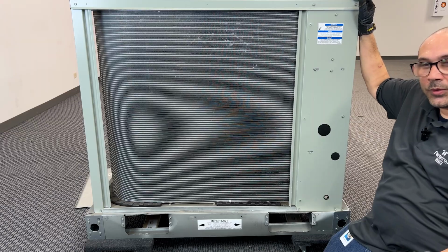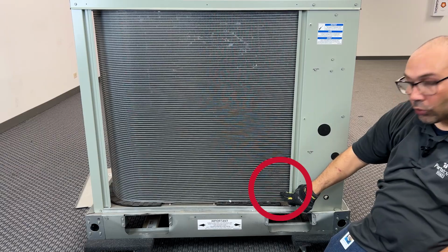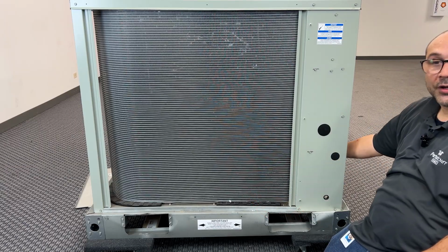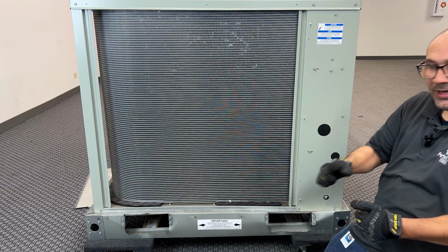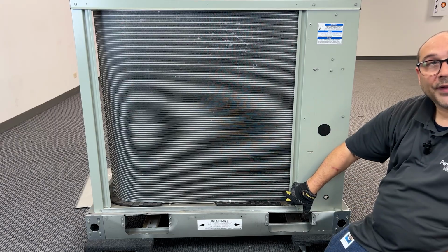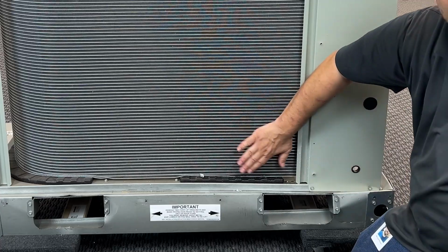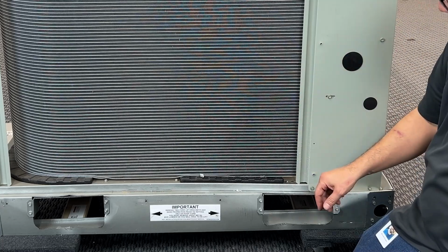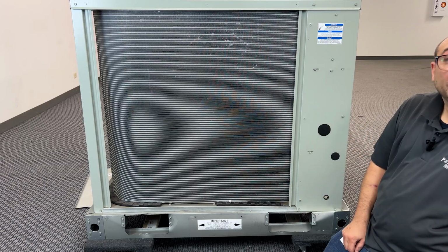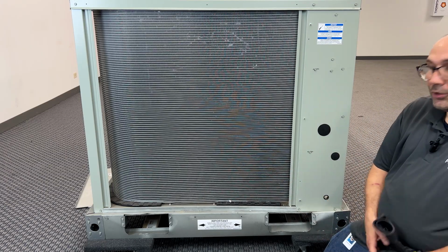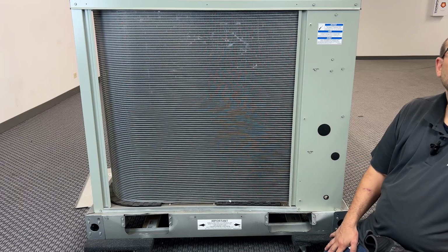One of the more common places for condenser coil leaks can be right down at the coil corner, right before the compressor comes in. Usually that happens because of a jolt of the compressor, putting stress on the coil down at the bottom here. In this situation, the first thing I'm going to look for is a discolored coil, and it'll give me a place to look. If I look here, oh hey, there's oil, so I know my leak is somewhere in here. Now I would go with my bubbles, pump it up with nitrogen, and see exactly where that leak is.